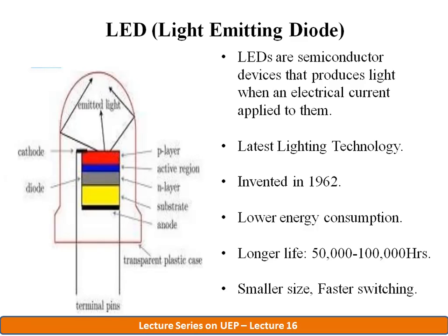The current is generally about 200 to 1000 milliamperes, and also includes supplementary electronics for dimming or color correction control. Currently available LED drivers are typically about 85% efficient, so LED efficacy should be discounted by 15% to account for the driver.